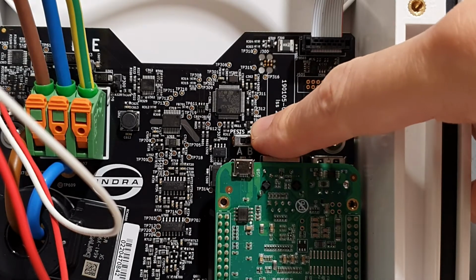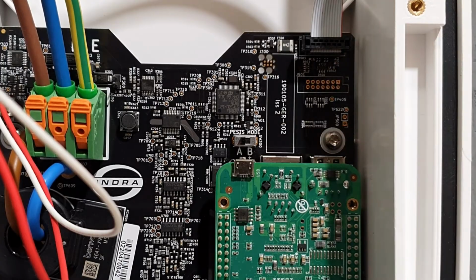The resistance of the earth electrode to earth shall be such that the maximum voltage between the main earthing terminal of the installation and earth, in the event of an open circuit fault in the PEN conductor of the low voltage network supplying the installation, does not exceed 70 volts RMS. Again, if you're installing a charger in this scenario, then you need to set the switch in the back to mode A. All the scenarios discussed so far have two things in common.